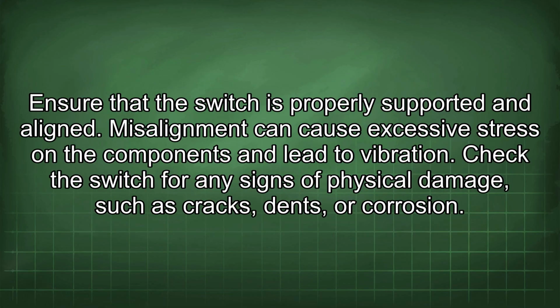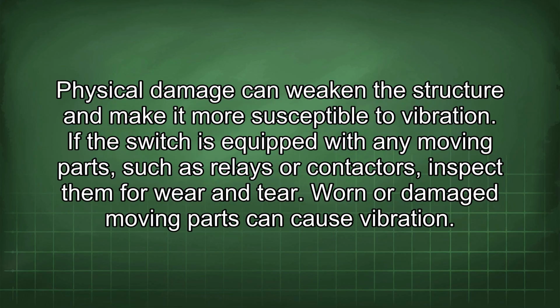Ensure that the switch is properly supported and aligned. Misalignment can cause excessive stress on the components and lead to vibration. Check the switch for any signs of physical damage, such as cracks, dents, or corrosion. Physical damage can weaken the structure and make it more susceptible to vibration. If the switch is equipped with any moving parts, such as relays or contactors, inspect them for wear and tear. Worn or damaged moving parts can cause vibration.